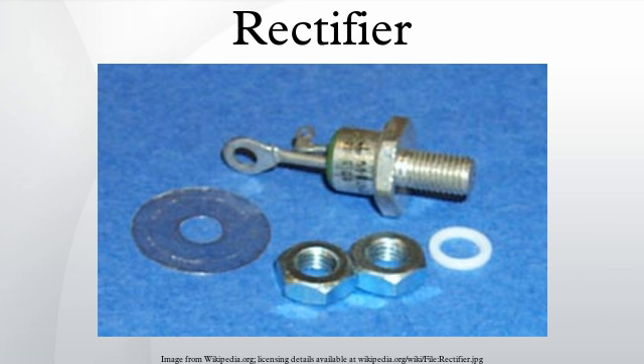The effect of supply inductance is to slow down the transfer process from one phase to the next. As a result, at each transition between a pair of devices, there is a period of overlap during which 3 devices in the bridge are conducting simultaneously. The overlap angle is usually referred to by the symbol μ, and may be 20–30 degrees at full load.